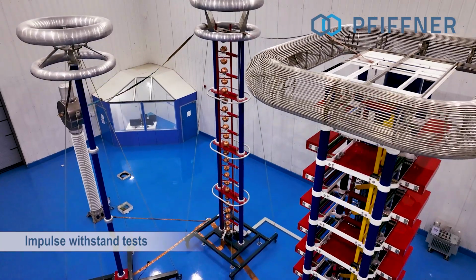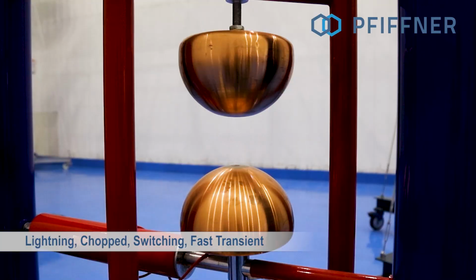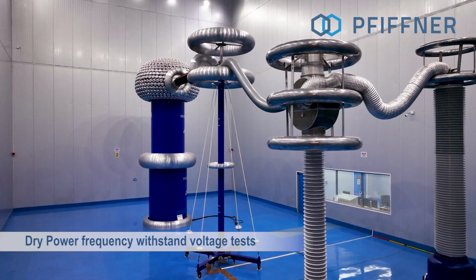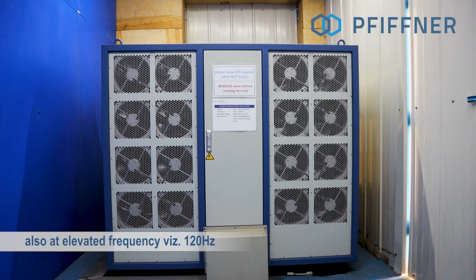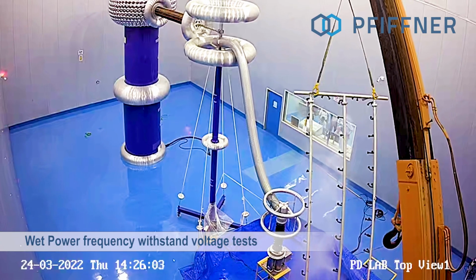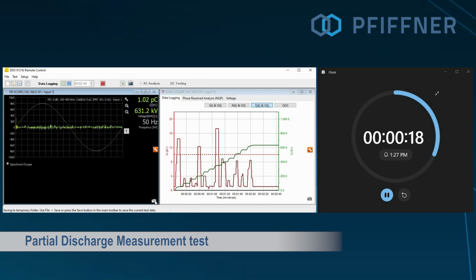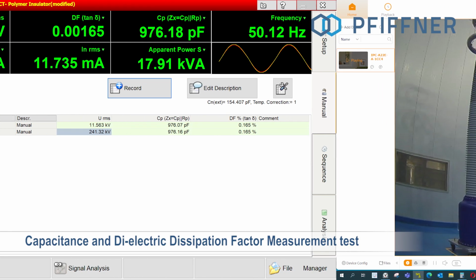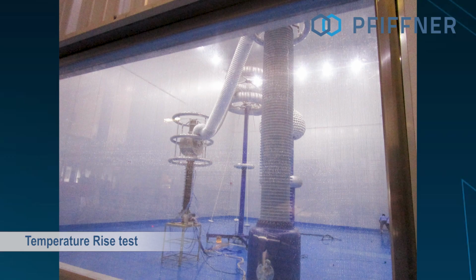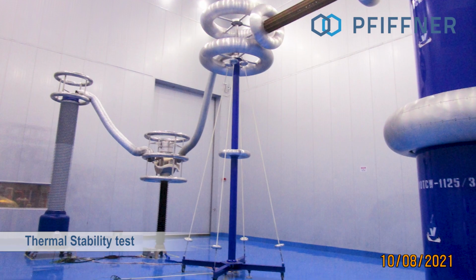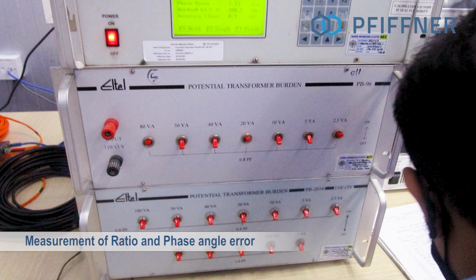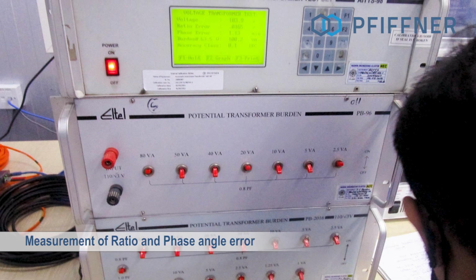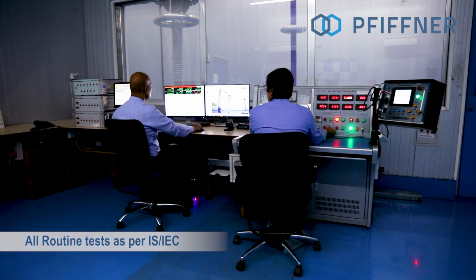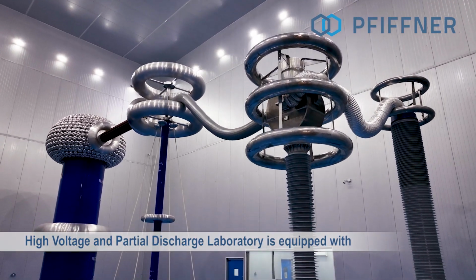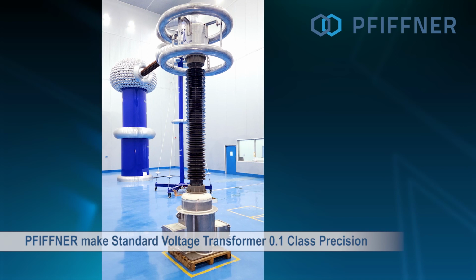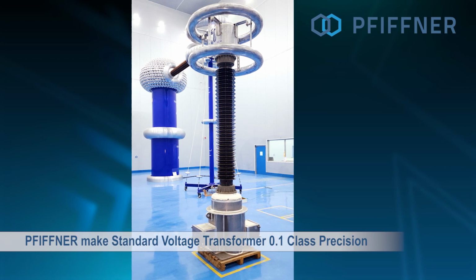Impulse withstand tests: lightning, chopped, switching, fast transient. Dry power frequency withstand voltage tests, also at elevated frequency, that is 120 Hz. Wet power frequency withstand voltage tests, partial discharge measurement test, capacitance and dielectric dissipation factor measurement test, temperature rise test, thermal stability test, temperature coefficient test, measurement of ratio and phase angle error, all routine tests as per IS, IEC. The high voltage and partial discharge laboratory is equipped with a Pfiffner make standard voltage transformer, 0.1 class precision.